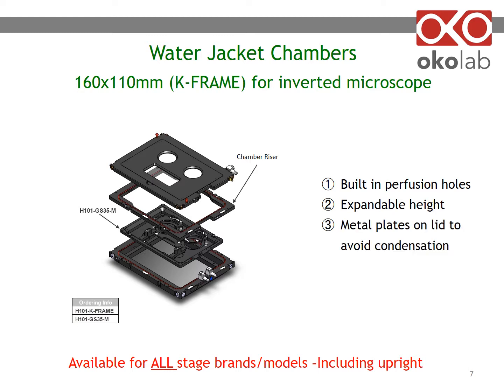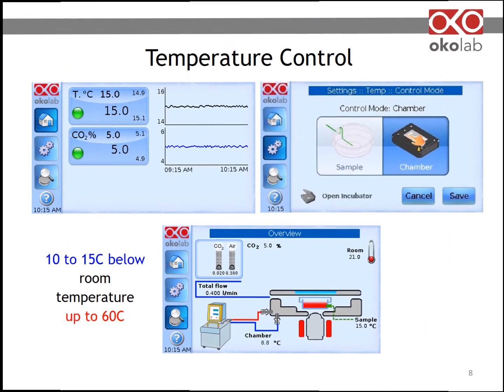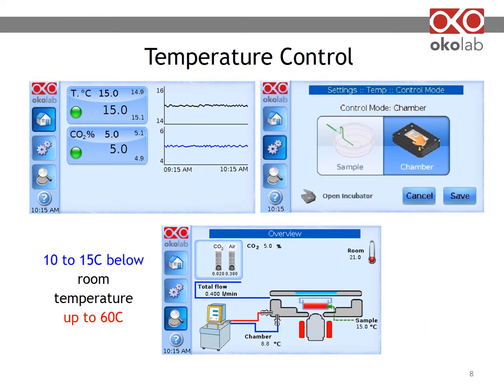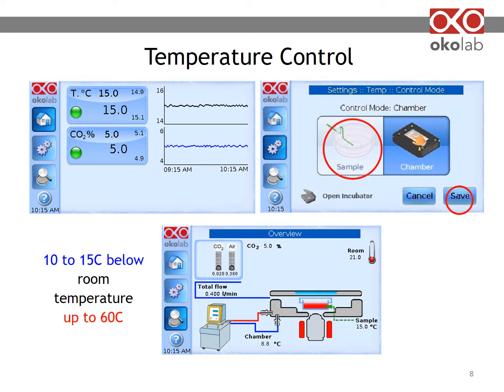The height of the chamber can be expanded using multiple chamber risers. On the lid, a suitable metal plate avoids condensation. Temperature is set using a touchscreen interface. You can operate the system in chamber feedback mode, or you can place the provided temperature probe in a reference well and set operating in sample feedback mode.